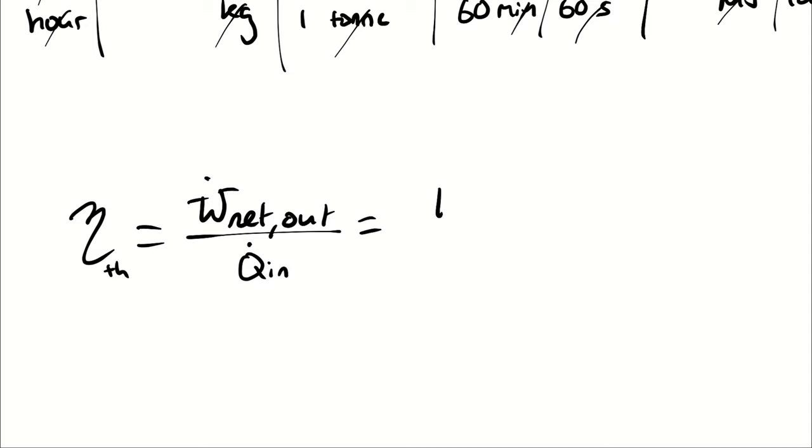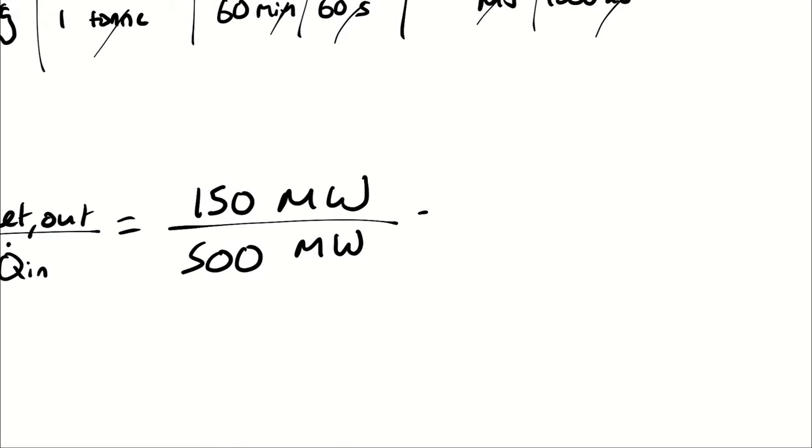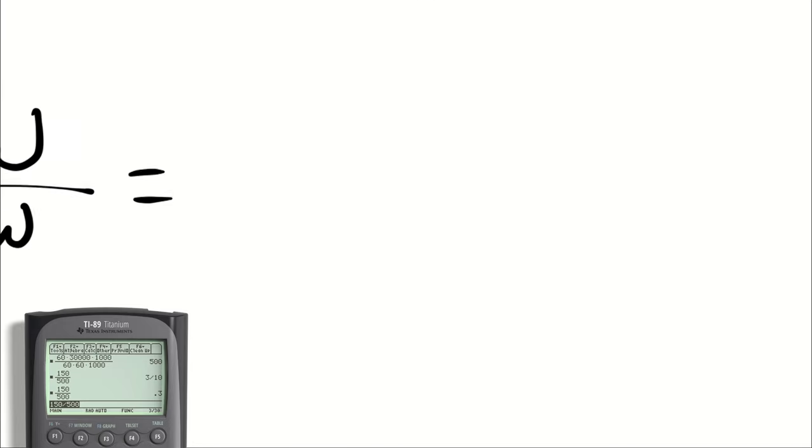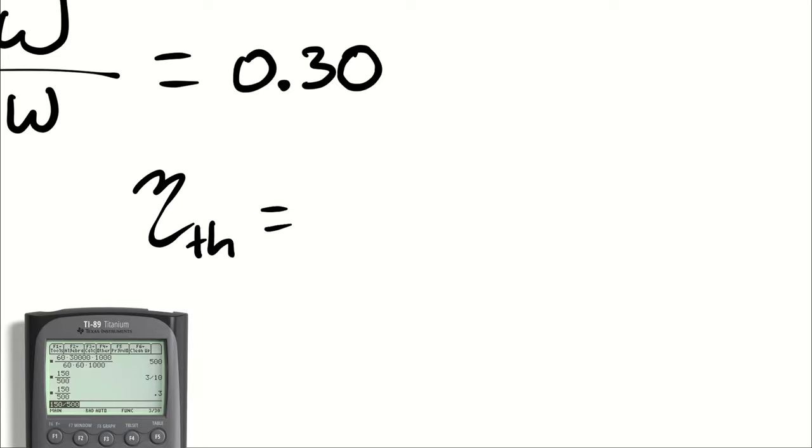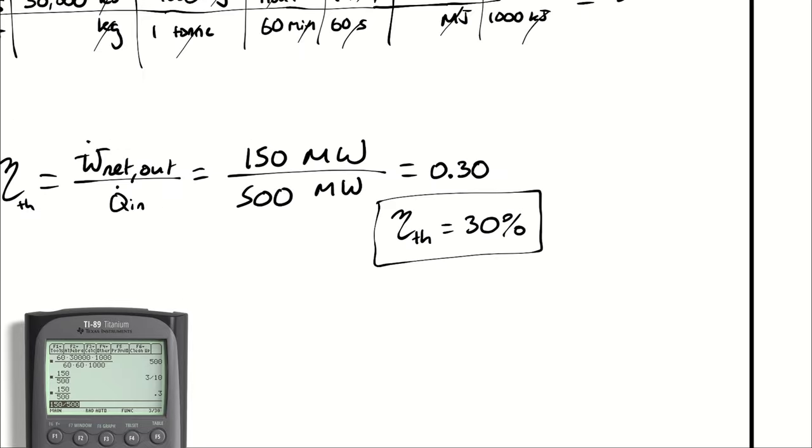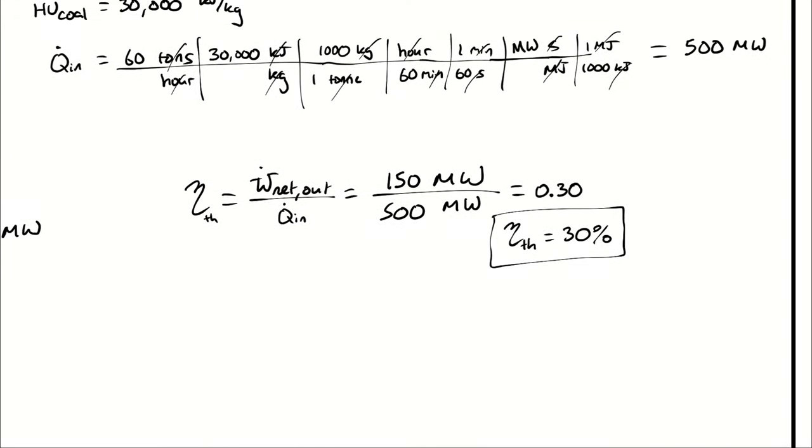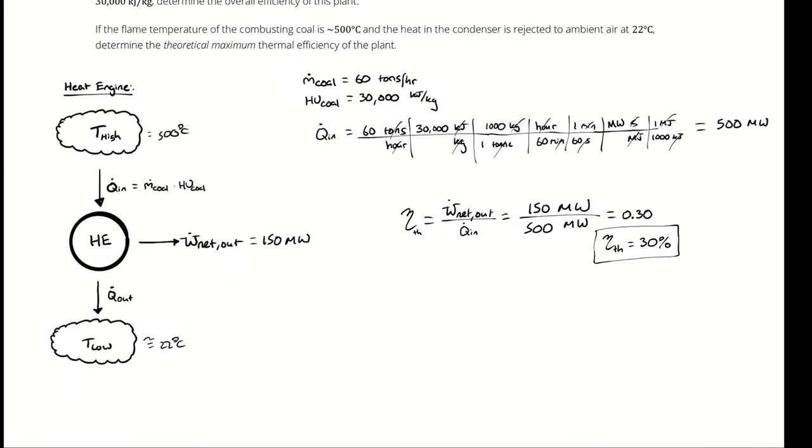Now we take our net power output, which we were told is 150 megawatts, and we divide by our shiny new Q_in, which is 500 megawatts. And we get a thermal efficiency of 30%. Just to verify, I will let the calculator second my calculation. So assuming that all of the coal produces 30,000 kilojoules per kilogram of heat transfer, and all of that heat transfer is being acquired for the purposes of this power production, the thermal efficiency of this facility is 30%.